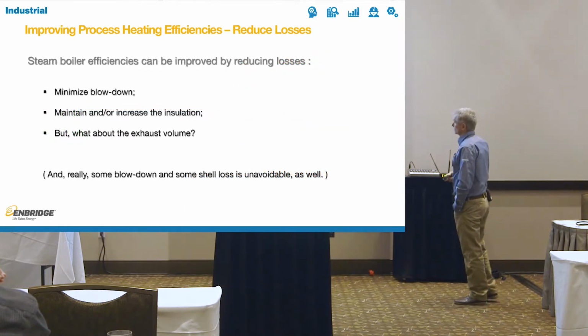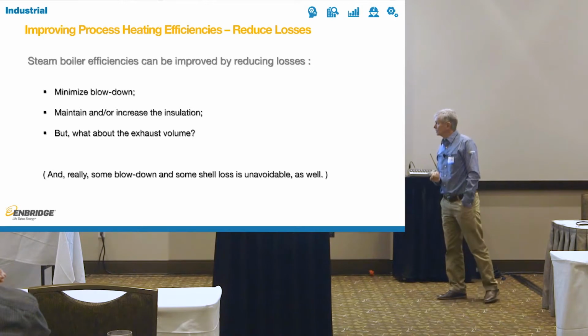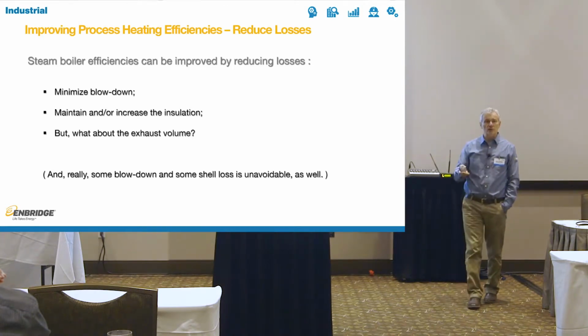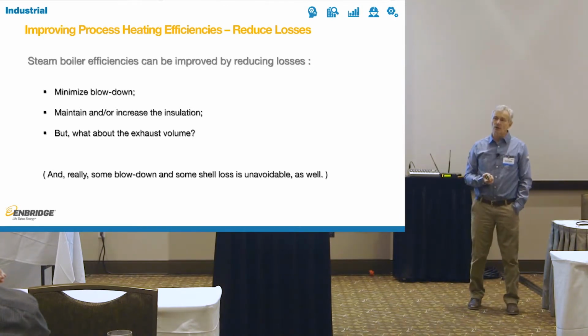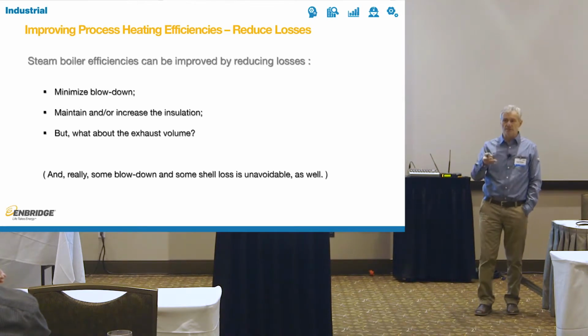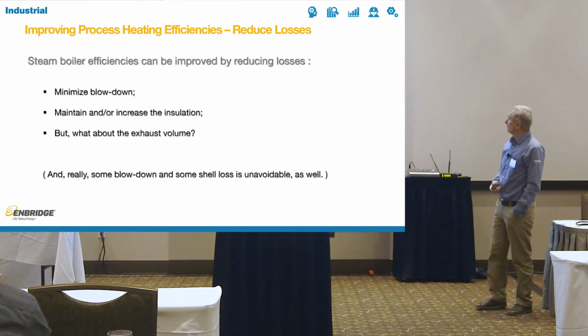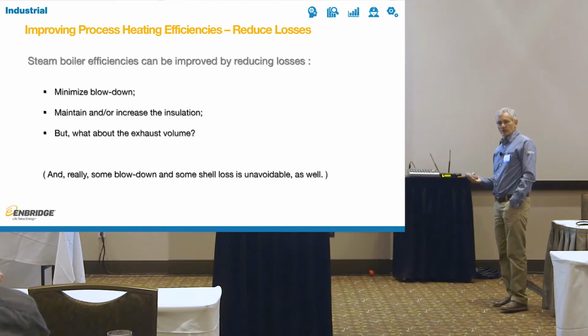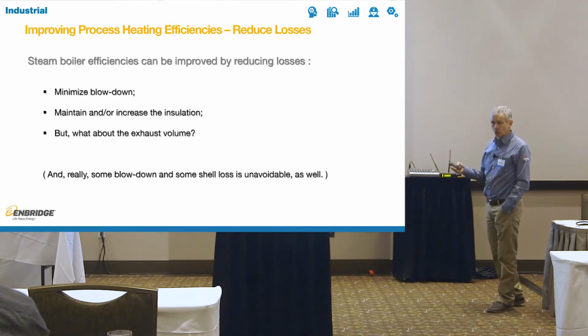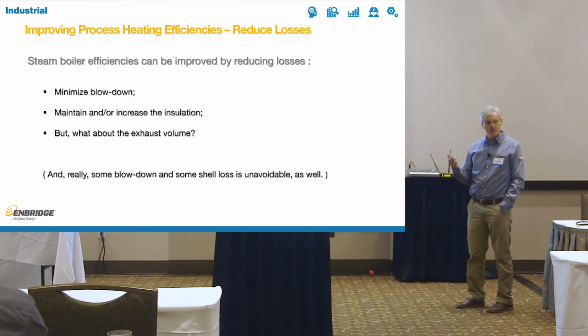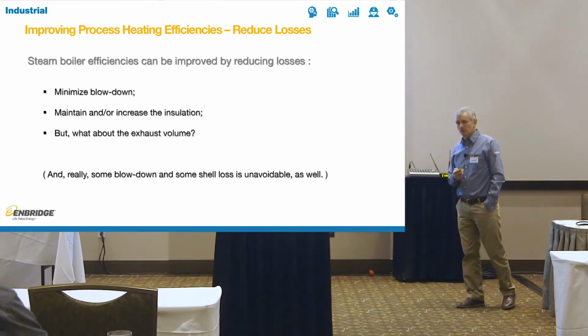So what do you do with those? How can you improve your boiler efficiencies? Well, you minimize the blowdown, because that's one of the ways you lose your energy. You heat it up, you create steam, and then you just blow it down the drain. You maintain or increase the insulation. Some of the boilers are old and have really torn insulation, so replace the insulation. Then there's exhaust volume.